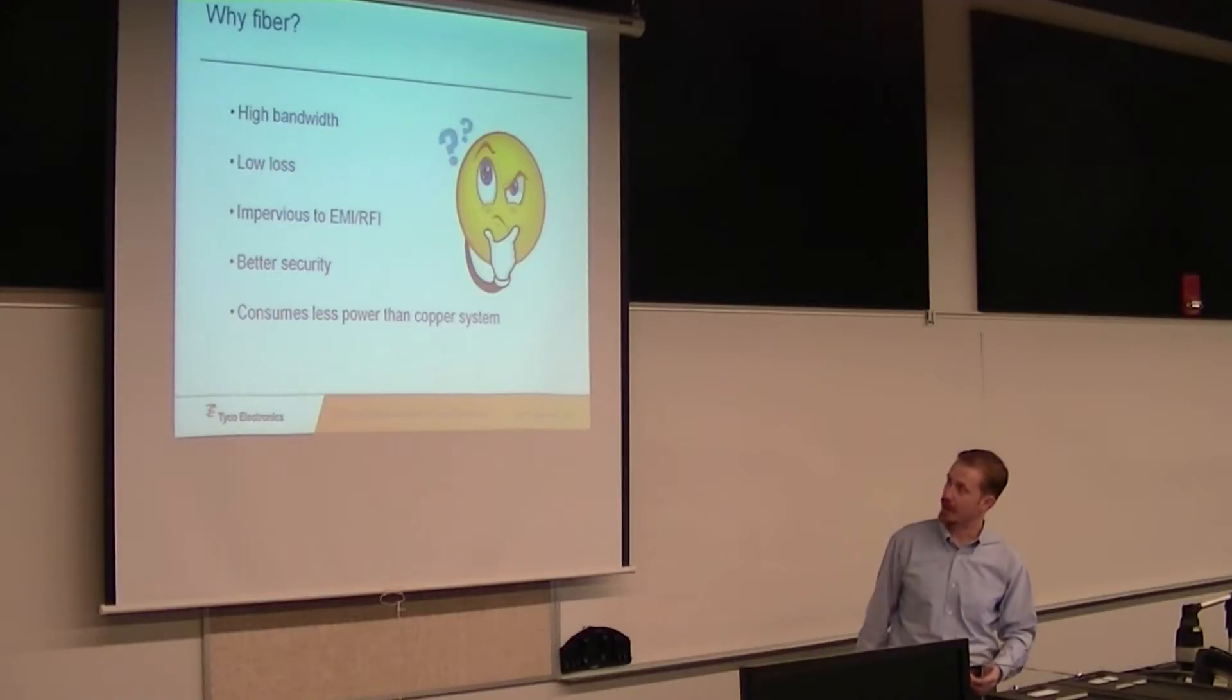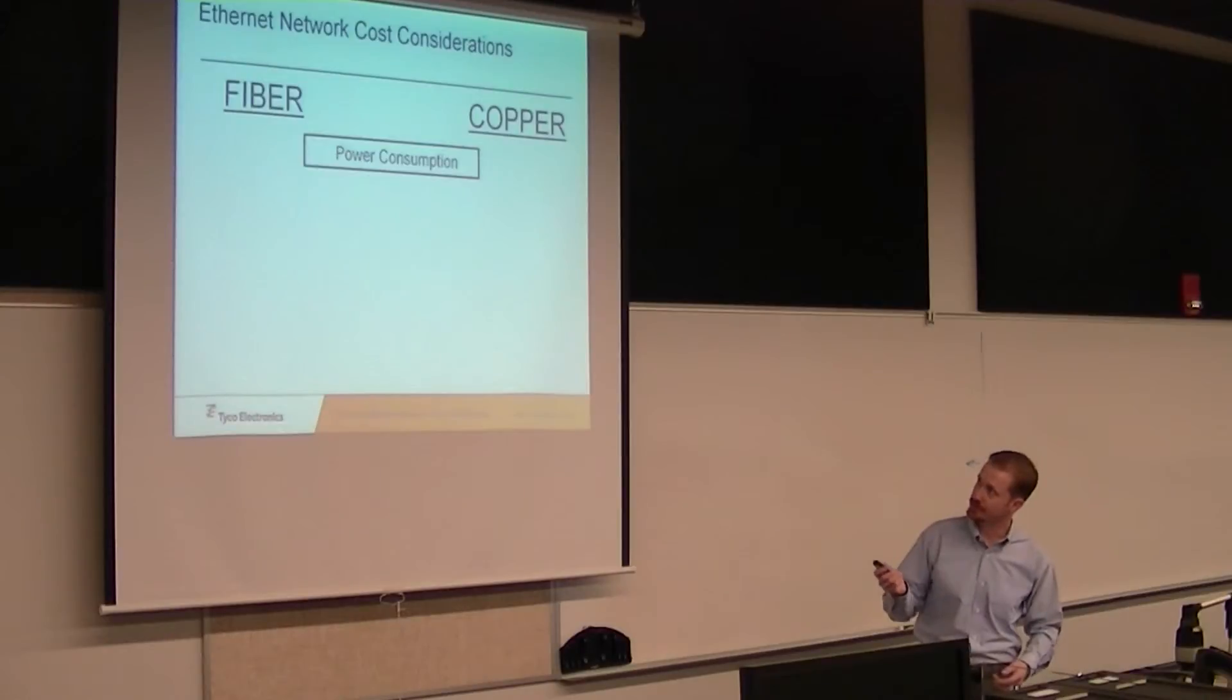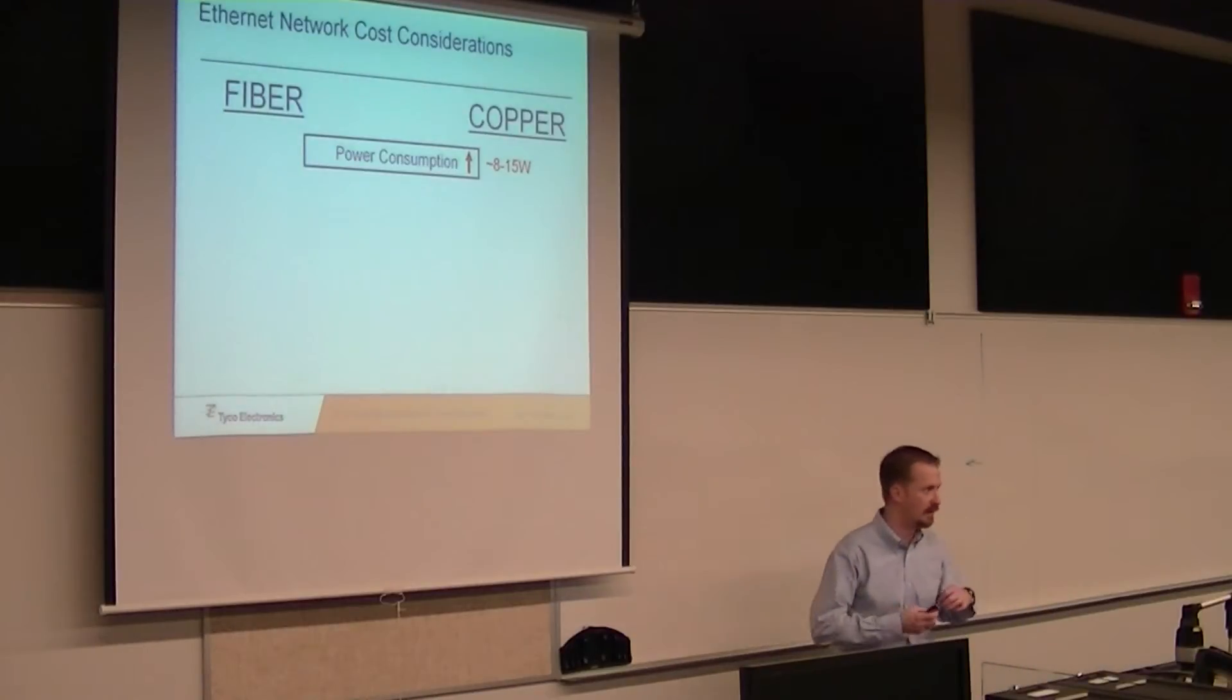You go in and put a T-tap or something like that into fiber, it's going to split your signal in half. And when you split that signal in half, it reduces quality on both ends, so it's immediately detected. That's why the government loves fiber. It consumes a lot less power than the copper system. We're going to cover cost considerations and power consumption. On a copper system, you're looking at about 8 to 15 watts per channel. But on fiber, you're looking at about 2 watts through your transceiver. Any time that you have power consumption, that's heat generated. So you need to cool that.